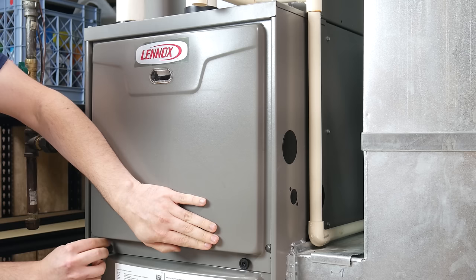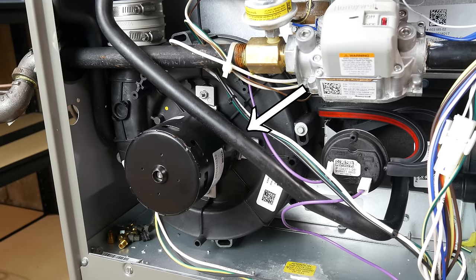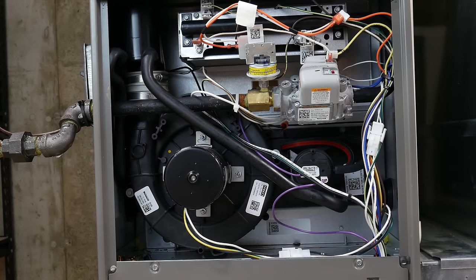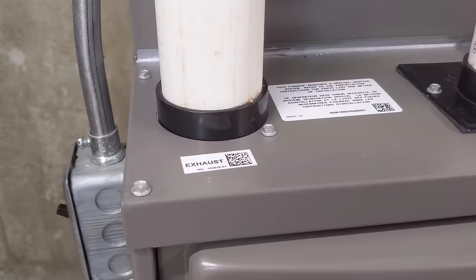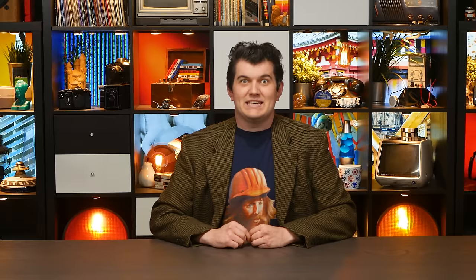Now we're getting into the more practical and safety bits of the furnace. If you've ever lived with a furnace like this, you'll likely have noticed that there are two blower motors. There's the big one that makes air come out of your registers. But before that one comes on, you hear another one. That's arguably the most important part of the furnace. This blower is called the draft inducer — and really it's more of a sucker. It pulls air, and later other fun gases, through the heat exchanger. In other words, it induces a draft. That air then gets pushed up through some sort of chimney where it will eventually exit the home, or, as is the case here, it exits through this PVC pipe. The draft inducer lives on the exit side of the heat exchanger, so it pulls air through the tubes, and what lives on the other side of those tubes are the flamethrowers.